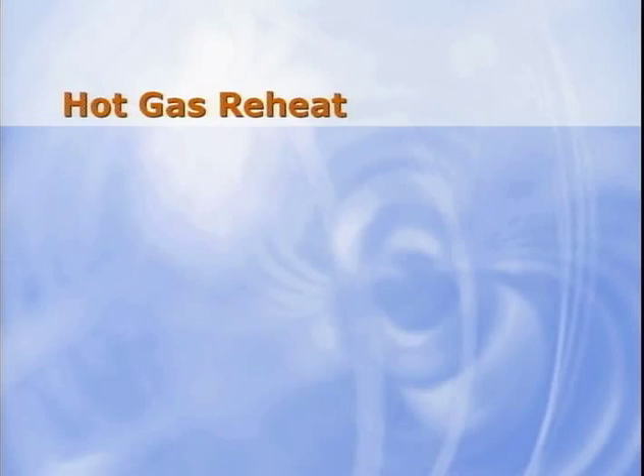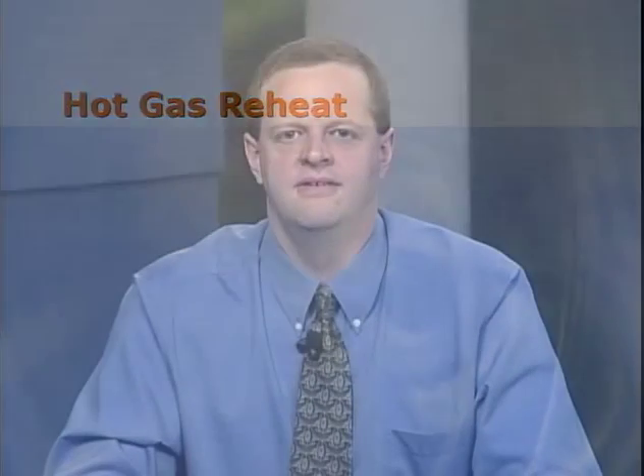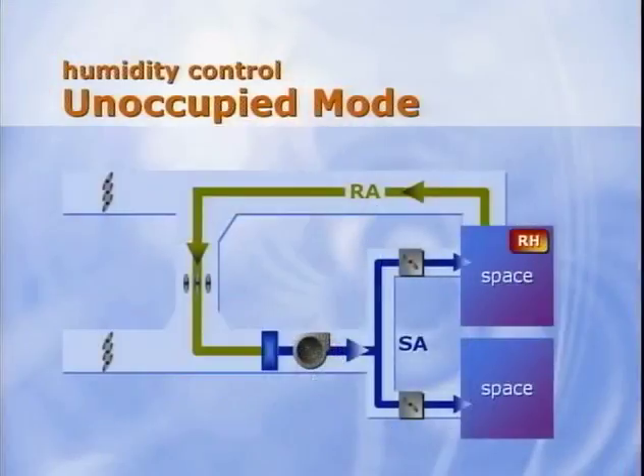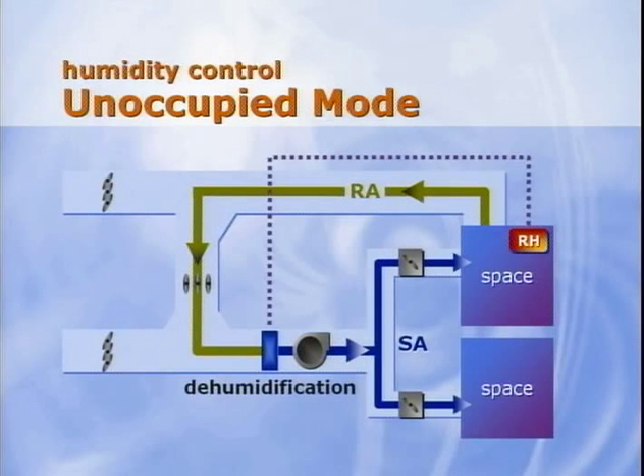Next topic, hot gas reheat. A VAV system typically dehumidifies effectively over a wide range of operating conditions because it continues to deliver cold, dry air at part load. However, controlling humidity levels isn't only a priority when the building is occupied. When indoor humidity rises too high during unoccupied times, one option is to turn on the rooftop unit and dehumidify recirculated air to 55 degrees or so.